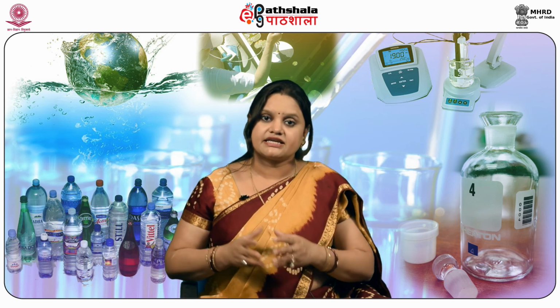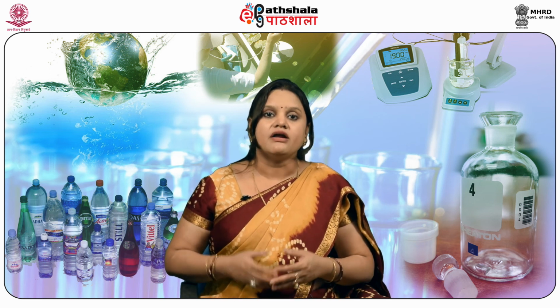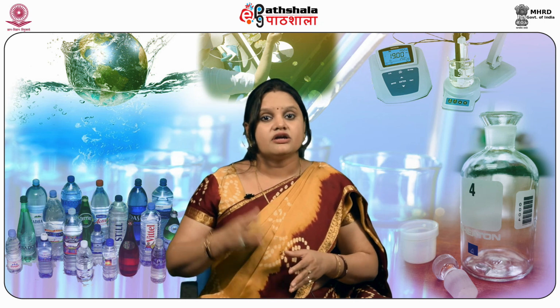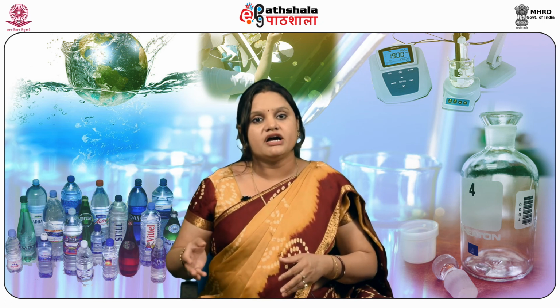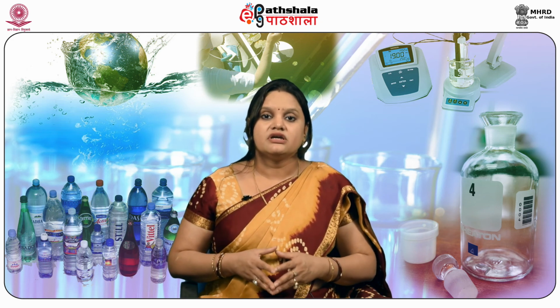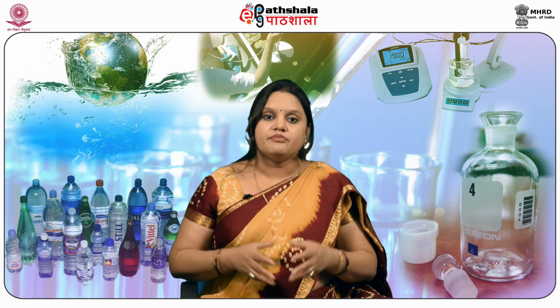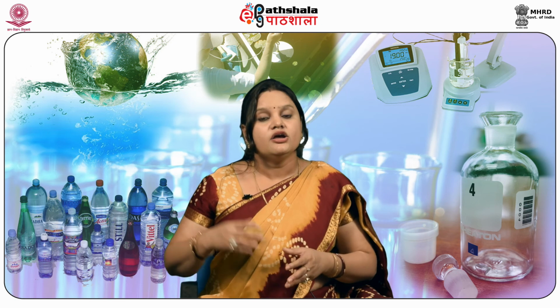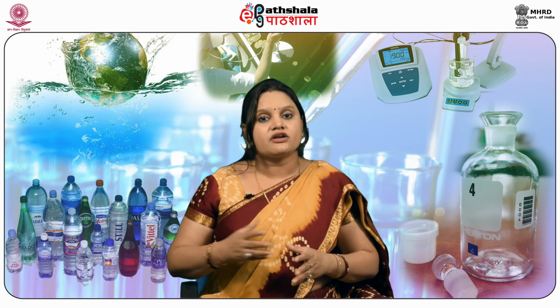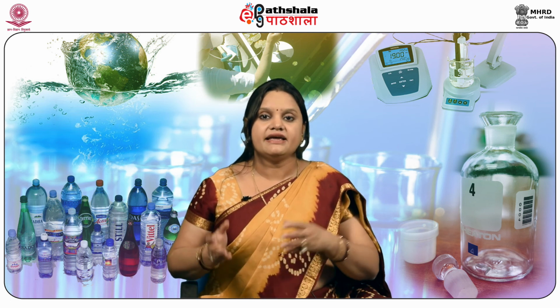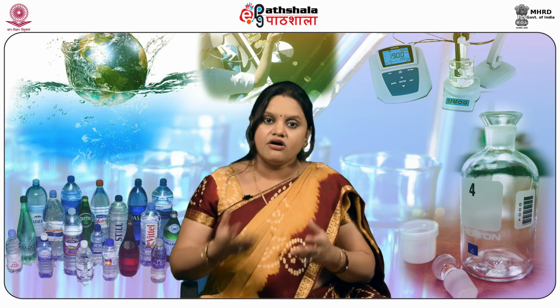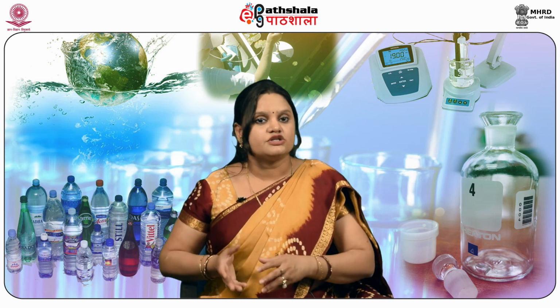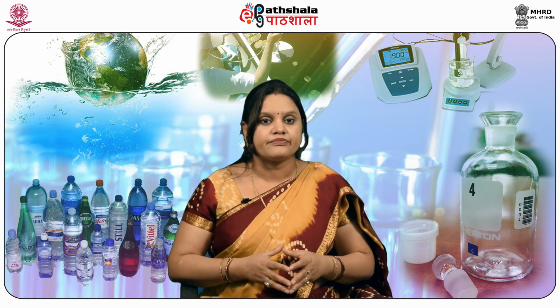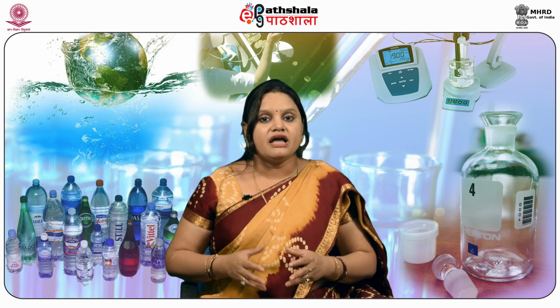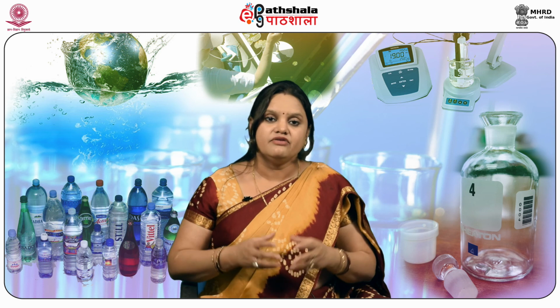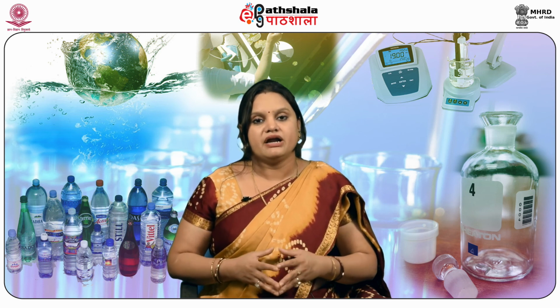Usually, disinfection is carried out with chlorine, bleaching powder, or hypochlorite. The basic chemical, chlorine itself, is an electrochemical product from which the others are produced. Even if chlorination is done, hypochlorite is the effective reactant in more instances. The electrolytic chlorination or the hypochlorination is a simple, cost-effective and on-site process which eliminates the transport and storage of the gaseous chlorine. User-friendly portable chlorine and the hypochlorite generators are available for water and the effluent treatment plant.